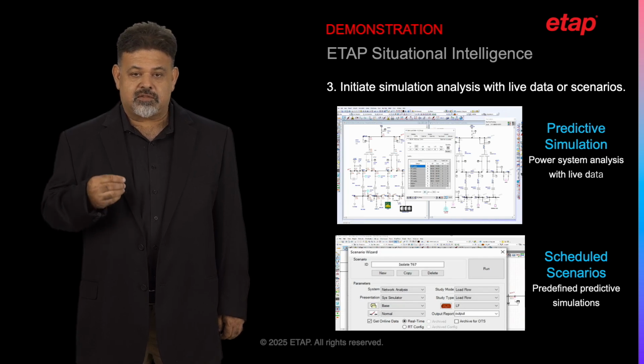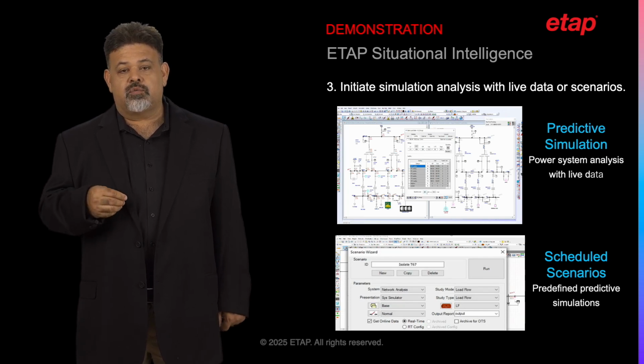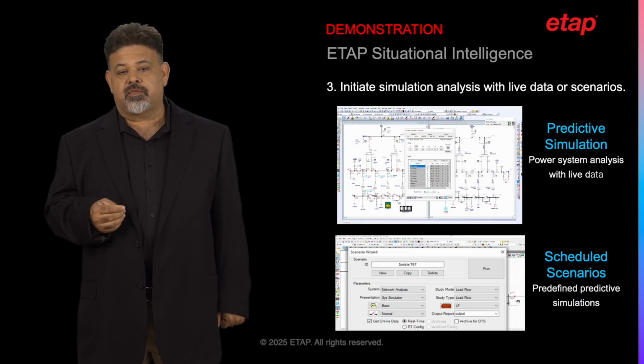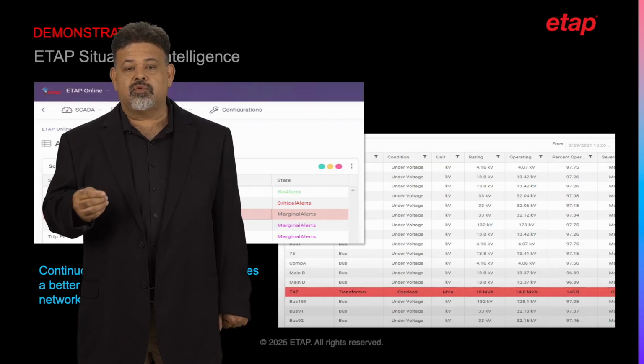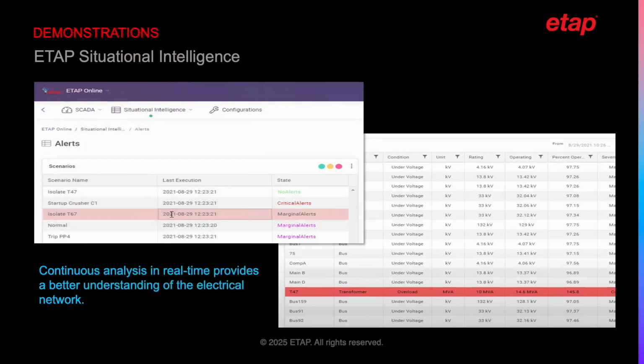Examples of such actions can include isolating a transformer, where the operating load may cause an overload in the system. Another example is the start of a large motor that can cause instability on the system due to required power during startup. These scenarios are then visualized by the operators and observed if there are any potential unsafe conditions for specific events. This simple simulation can provide a short summary to the operator if proceeding with an action may be safe or if alerts are detected, and it may require an alternative course of action. This continuous power analysis in real time provides a better and simpler understanding of the network.